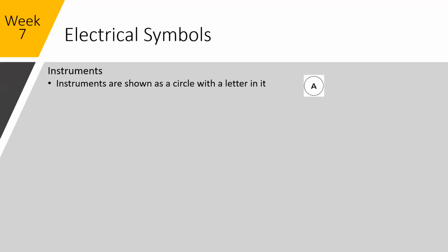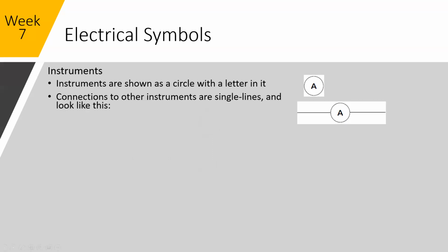Okay. So instruments. So instruments are typically shown with a circle with a letter in it. A here would be an amp meter. Connections to other instruments are single lines that look like lines coming in and out. These also indicate wire. So there could be a note on this telling you that this is red wire 16 gauge AWG, which would specify the color of the plastic or coating on the wire, the amount of copper and what the copper consists of, whether it's solid core or stranded wire.